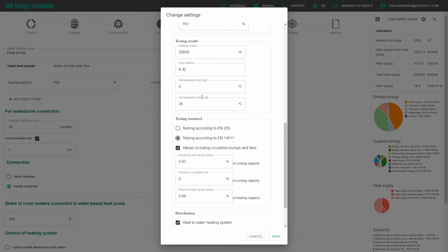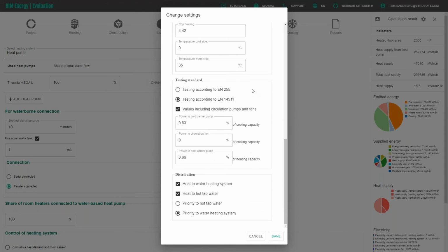we can calculate the exact operating conditions for every hour. We're actually doing it in smaller steps, but depending on how hot a temperature we need to deliver, how cold the heat source is, and how much power output, we can calculate how much electricity we need.